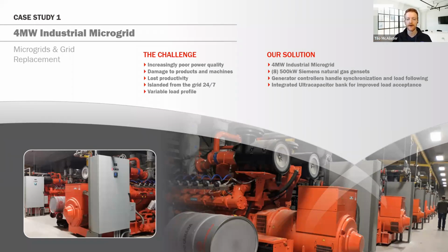But to solve the load following problem, we integrated a line of ultracapacitors that would be able to take the hit of that largest piece of machinery that made that massive spike every 15 seconds. So when that press comes on, the spike in demand is met by the ultracapacitors, and once the spike is over, there's enough time for them to recharge from the generator sets to supply that demand when it comes along again.